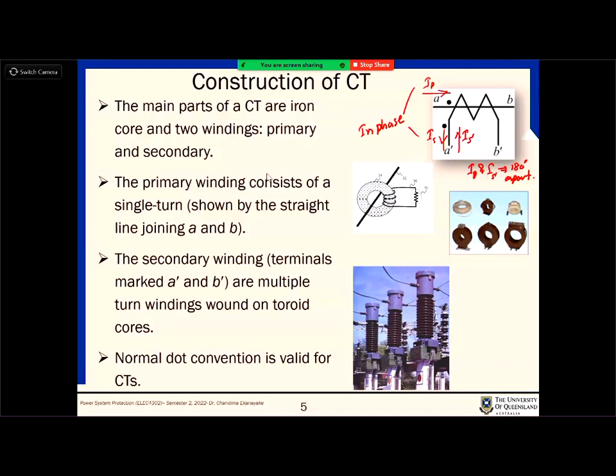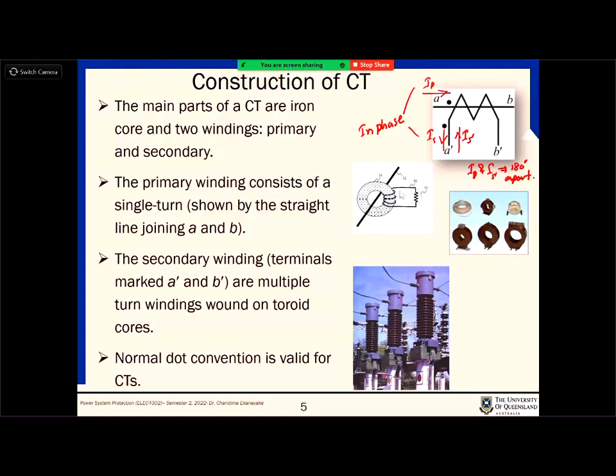Yeah, so from the construction point of view, the primary winding is only a single turn, because it's just one wire. The secondary terminal will have multiple turns, depending on the ratio that you want to maintain. And then this dot convention, which I mentioned here, it is valid for normal transformers or any winding, right? So it is the same convention. Current going into the dot, current coming out of the dot in the other winding, they are in phase.